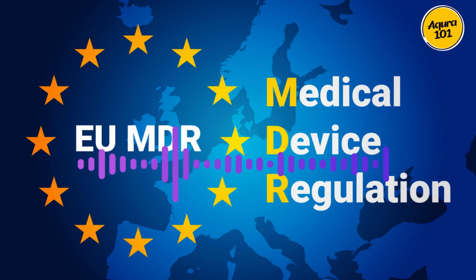It is. And importantly, the MDR emphasizes the need for collaboration and information sharing between competent authorities in different member states. That makes sense. A device that's deemed unsafe in one country shouldn't be allowed to be sold freely in another country. Exactly. The MDR establishes mechanisms for exchanging information about market surveillance activities and coordinating responses to non-compliant or unsafe devices. So if one country finds a problem, others can quickly take action to protect their own citizens. It's about working together to ensure a consistently high level of safety across the entire EU.